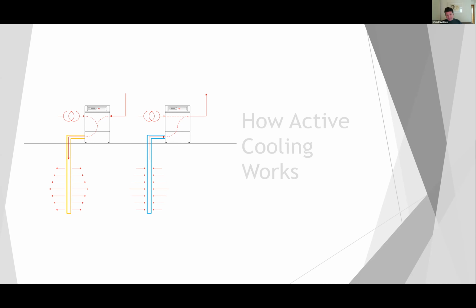It can be done in one box, as I've shown here, with a reversible heat pump. And effectively what that does is it swaps the heat exchangers round on the compressor. So that's a reversible system. Or it can be done more simply by having two heat pumps, one dedicated to cooling, one dedicated to heating, and sharing a communal ground array. It's all about horses for courses, and there are advantages and disadvantages to both approaches, but they're entirely valid. Obviously, as we build bigger systems, we may have more heat pumps connected to the ground array.